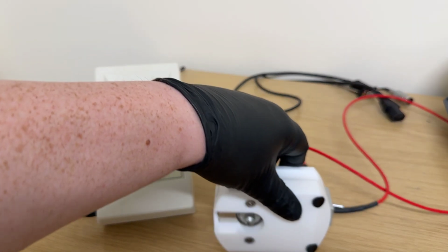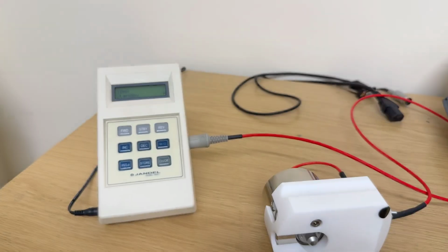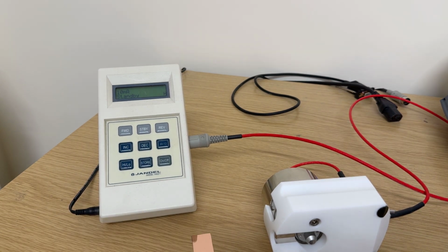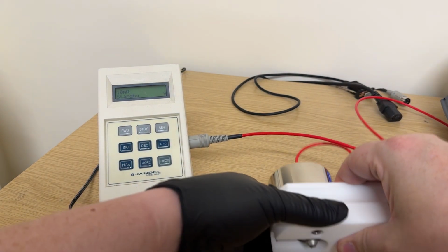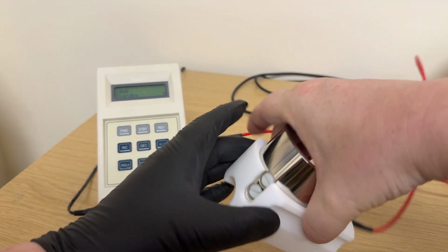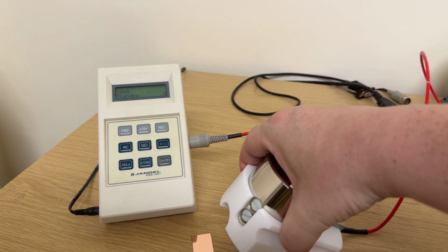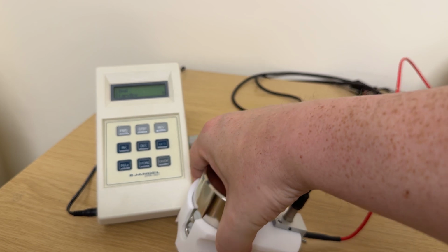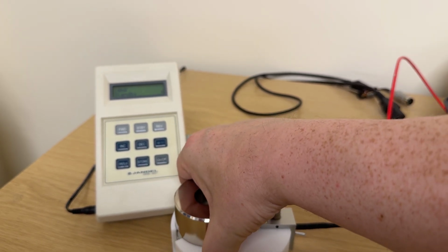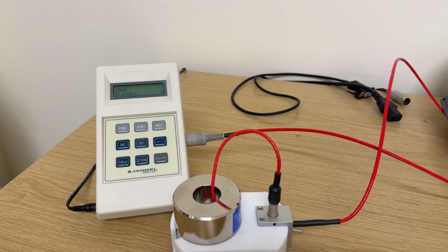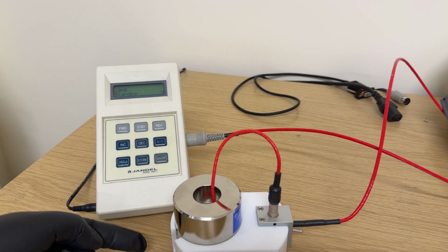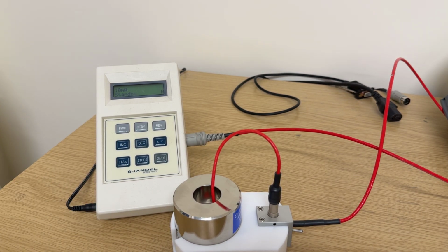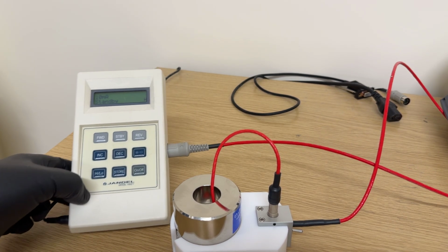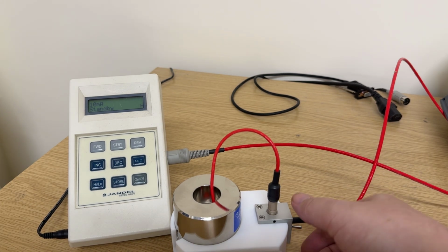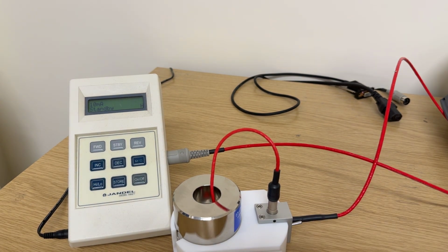When making a measurement, the hand applied probe should be introduced to the sample by rocking it about the rear axis, down and onto the sample. You can check the contact point of the needles by looking at the front of the unit where there's a cutaway to see where the needles contact the sample. I'll switch the switch to R so that we can make a measurement.